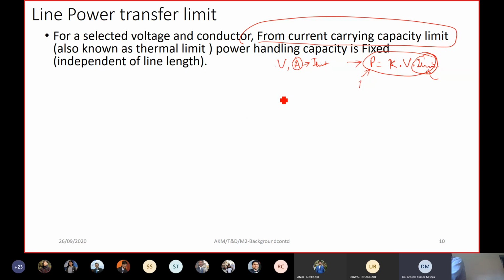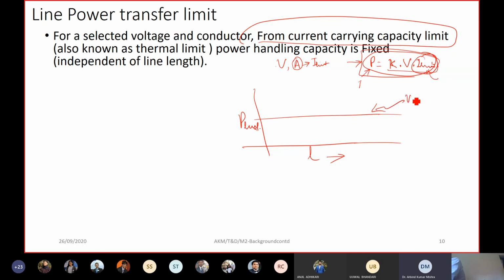If you plot it again, with L on one axis and P limit on the other, the thermal limit will be independent of the line length, isn't it? Because in this expression we do not have any line length term — this is for a given voltage and a fixed conductor size.